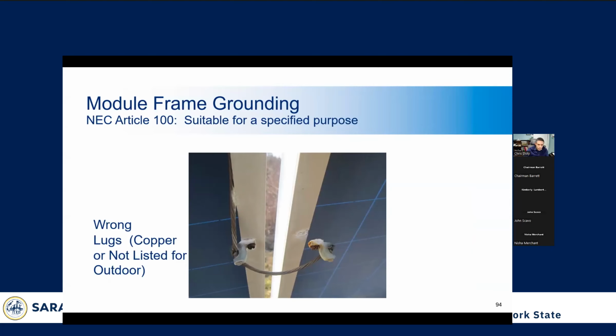So here's an example where a contractor attempted to accomplish the bonding requirements with a copper lay-in lug on aluminum frames. However, as you can see, they've corroded, and the copper lug has actually disconnected from the module. So this module is no longer connected to the ground path, or bonded. You can also see that they did the same thing over here. Looks like it's not going to last that much longer. And then eventually this one will also be disconnected. You can see more corrosion right here.